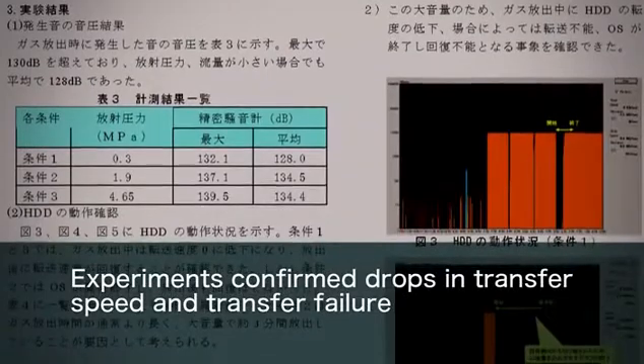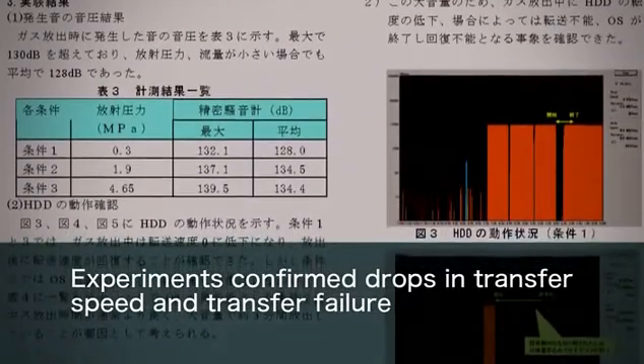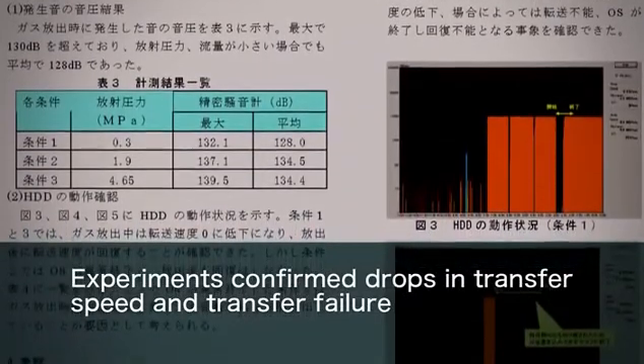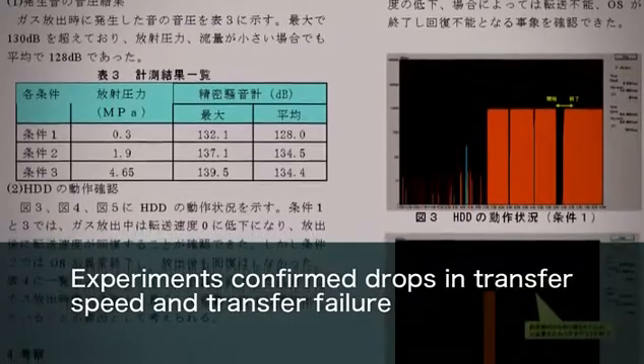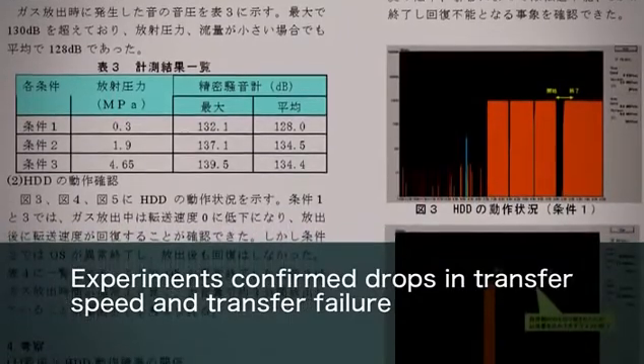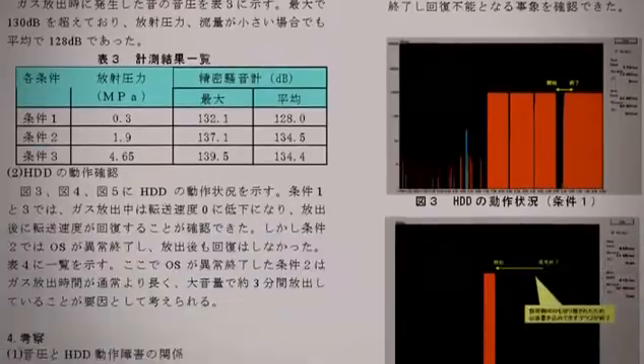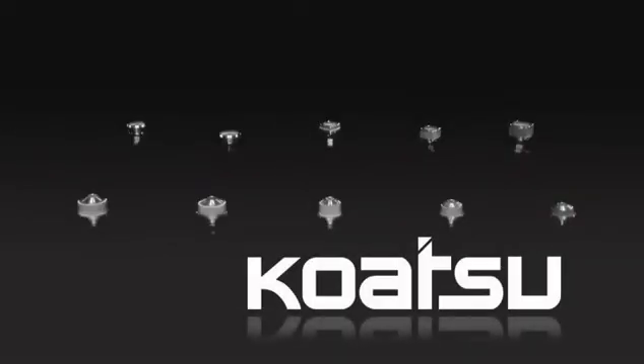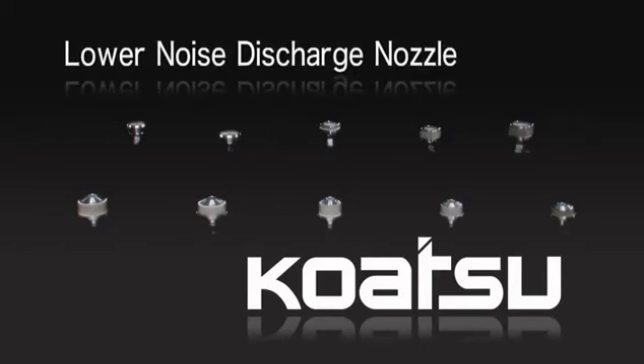Experiments have confirmed that during gas discharge, there may be a drop in hard disk transfer speed, transfer failure, and an abnormal shutdown of the OS, leading to an inability to recover data. This is not something which affects fire suppression performance. However, we at KOATSU felt this was a situation requiring an urgent response, and we began development of a lower noise discharge nozzle. The result is our new product.